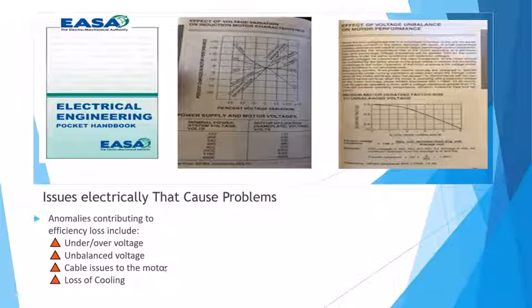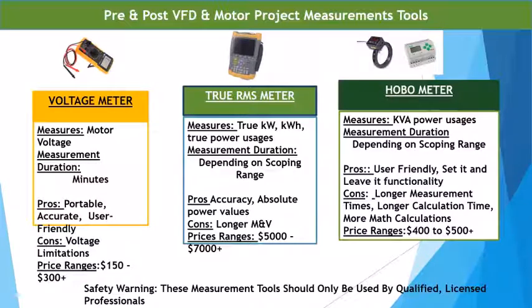This is output cabling of motors. Or, did it just simply lose its cooling? Did it have a blower on it? Did it have the fan on the motor, which wasn't bringing enough air across it? Or was it in too hot of an environment, and the winding design wasn't designed heavy enough?